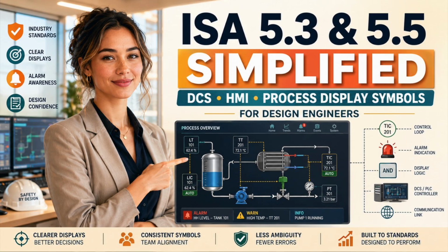A communication failure may freeze the last good value on the display. If that number continues to look live and valid, the display is presenting outdated information with the authority of current process reality. Imagine a tank level frozen at 52% while the real level has climbed above 90%.